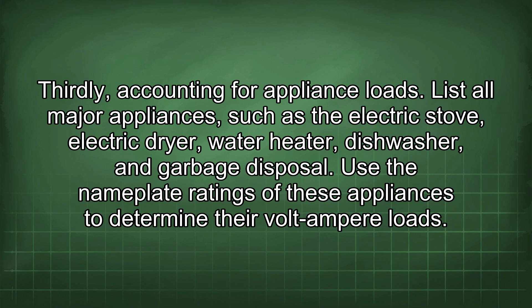For the electric stove, if the nameplate rating is not available, you can use the NEC table 220.55, which allows for demand factors based on the number of cooking appliances. For the electric dryer, use 5000 volt amps or the nameplate rating, whichever is higher.